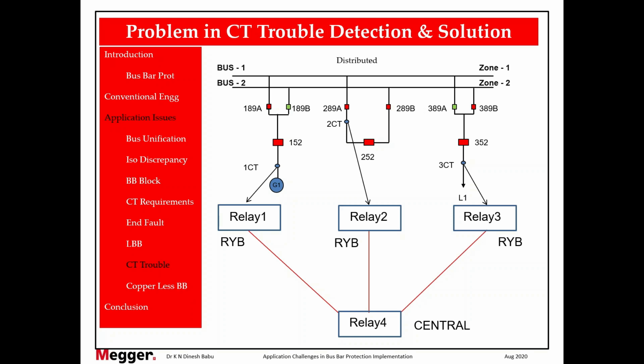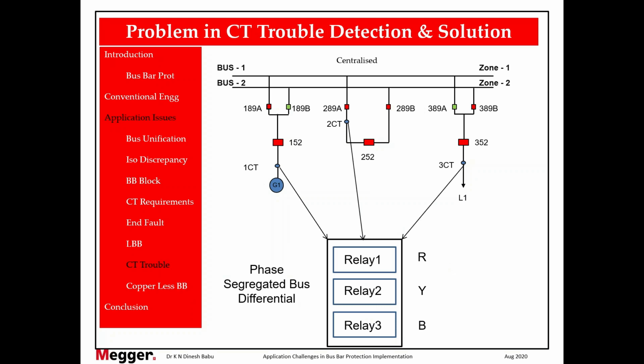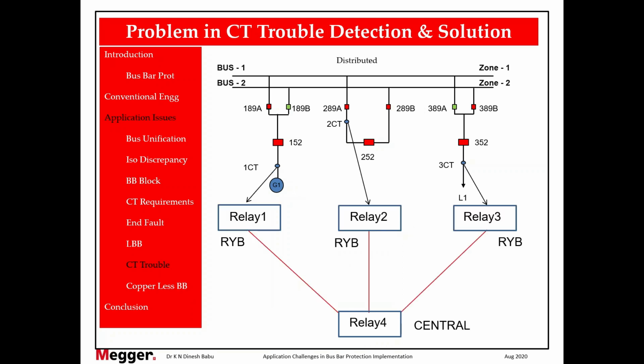See, when all the three phases are available in one relay, then the facility of calculating symmetrical components, that is positive sequence, negative sequence, and zero sequence current, is possible. Whereas in the case of the centralized relay, the symmetrical component calculation is not possible because it is not available in the same relay. It is available in independent relays. So why should we have the symmetrical components? What is the benefit of having symmetrical components in a bus differential system? The advantage is when there is a CT trouble condition, the relay will be able to identify it using a simple logic, a two-input AND gate.